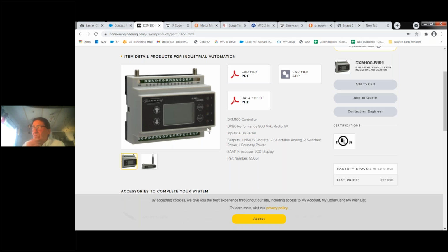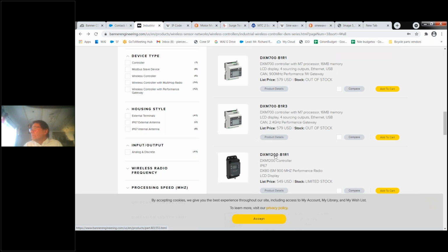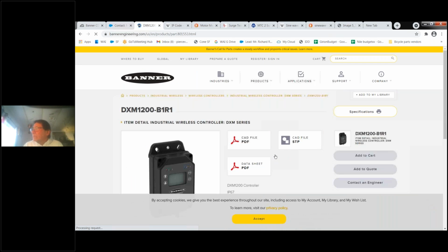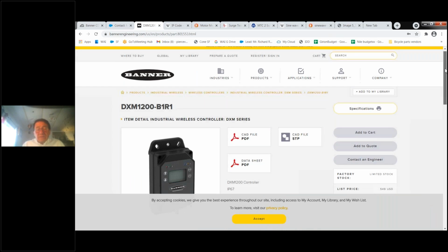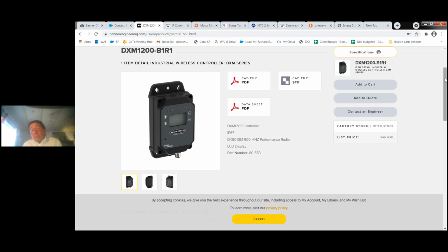And most of the manufacturers out there who offer these wireless nodes, if you will, offer both versions. Now, I will say this. We can use this and wire the other non-VFD devices directly into the node and boost them up and show them on the graphical user interface. Or what we can do is we can go back to this, sorry for the update rate, robust outdoor unit. And let's say you have a couple of other analog sensors. As you know, the IQ1000 and the IQ-U1000 have analog inputs. You can wire them directly to the drive and via the Modbus communication, get that data up to the internet.